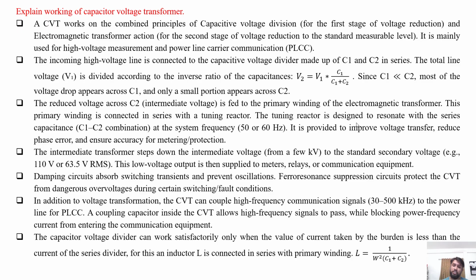Damping circuits absorb switching transients and prevent oscillations. Ferroresonance suppression circuits protect the CVT from dangerous over voltages during certain switching or faulty conditions. In addition to voltage transformation, the capacitor voltage transformer CVT can couple high frequency communication signals, that is from 30 to 500 kHz value of the frequency, to the tower line or the power line for the PLCC, power line carrier communication. A coupling capacitor inside the CVT allows high frequency signal to pass while blocking the power frequency current from entering the communication signal or equipment.